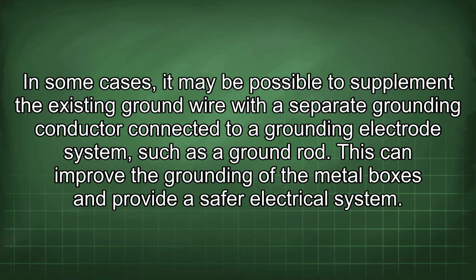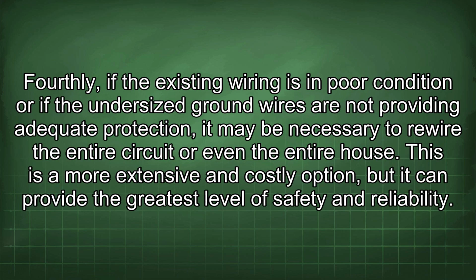In some cases, it may be possible to supplement the existing ground wire with a separate grounding conductor connected to a grounding electrode system such as a ground rod. This can improve the grounding of the metal boxes and provide a safer electrical system. Fourthly, if the existing wiring is in poor condition or if the undersized ground wires are not providing adequate protection, it may be necessary to rewire the entire circuit or even the entire house. This is a more extensive and costly option, but it can provide the greatest level of safety and reliability.